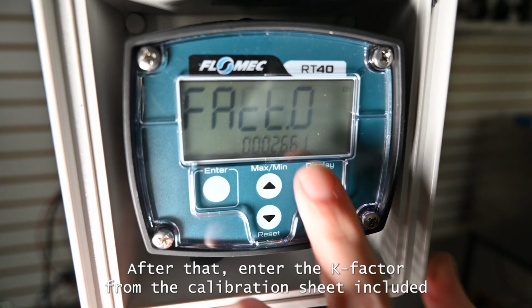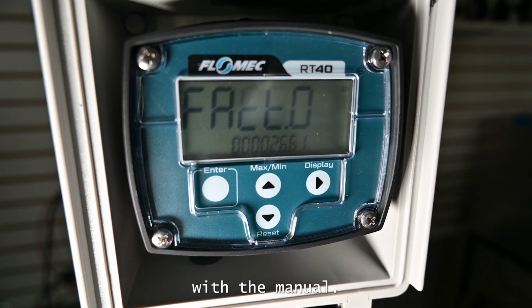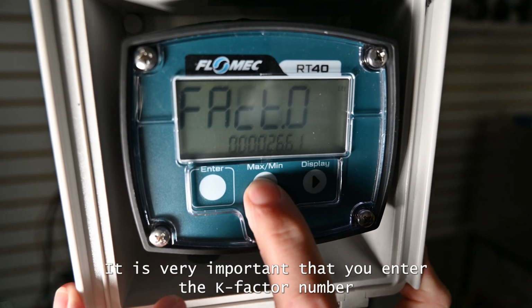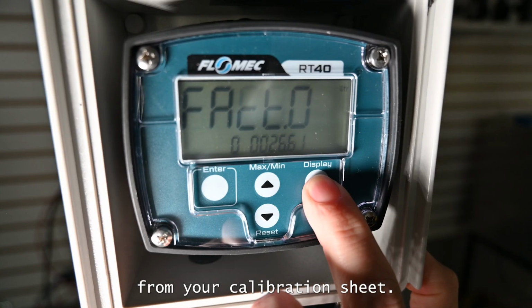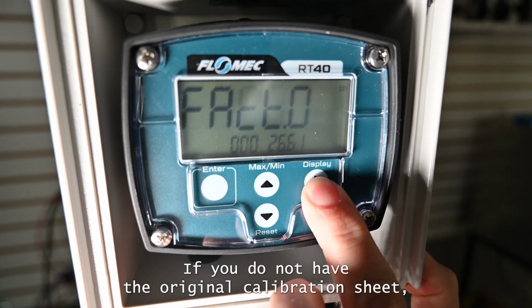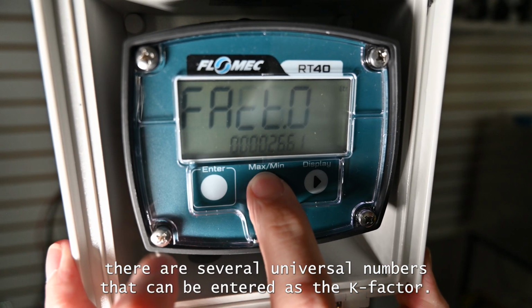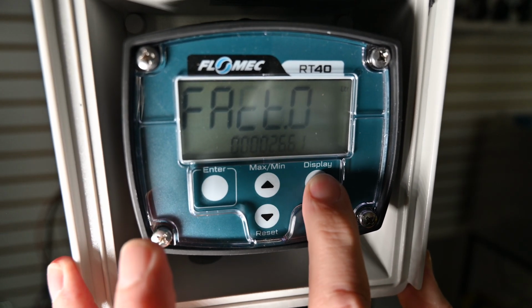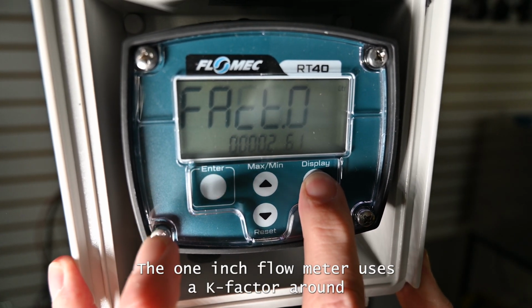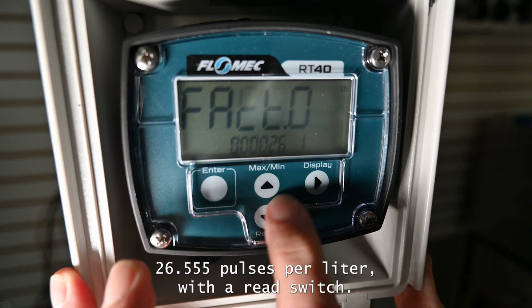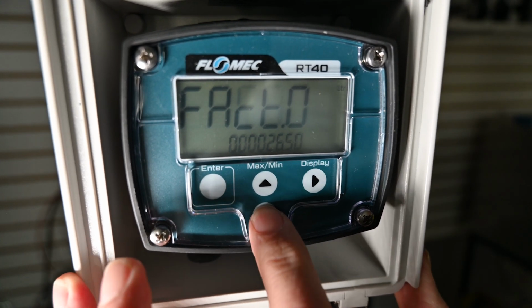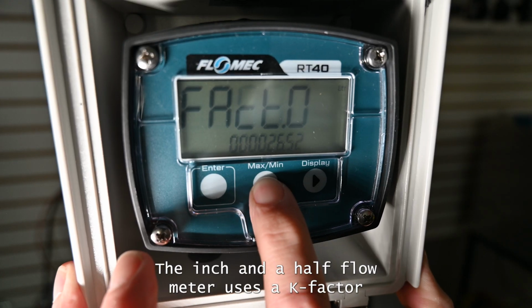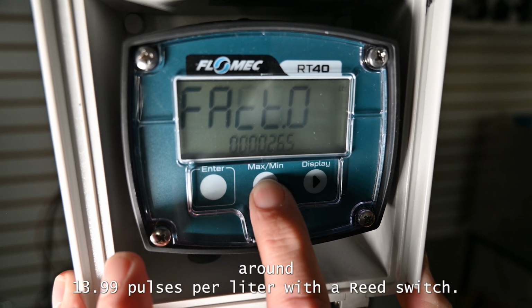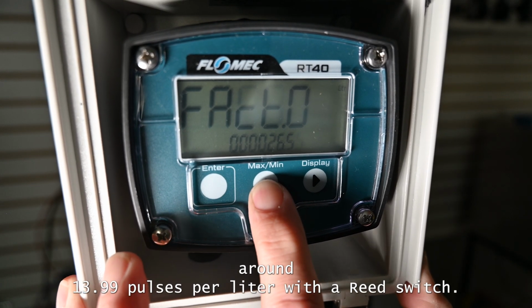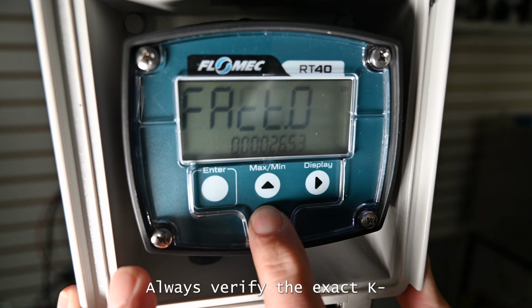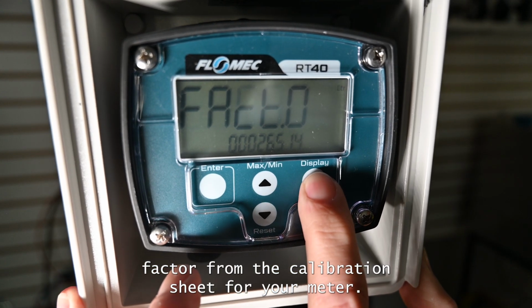After that, enter the K-factor from the calibration sheet included with the manual. It is very important that you enter the K-factor number from your calibration sheet. If you do not have the original calibration sheet, there are several universal numbers that can be entered as the K-factor. The 1-inch flow meter uses a K-factor around 26.555 pulses per liter with a reed switch. The 1.5-inch flow meter uses a K-factor around 13.99 pulses per liter with a reed switch. Always verify the exact K-factor from the calibration sheet for your meter.